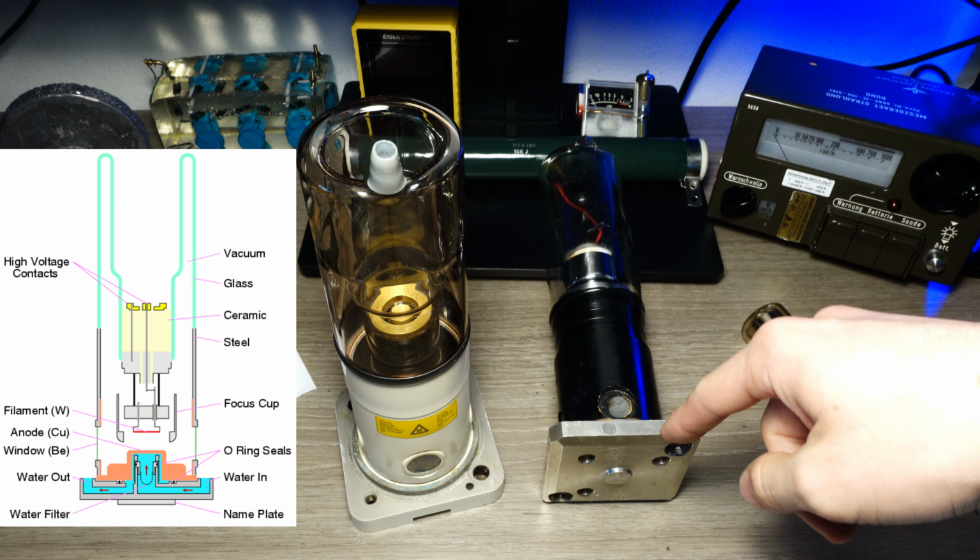And so after the X-ray tube, a filter is placed that is made of a specific metal to filter out the lower and the higher energy X-rays, and so you can have a much more monochromatic X-ray beam to do the different experiments. So now we're gonna disassemble these two tubes and see how the cooling is performed. So let's start with this one.